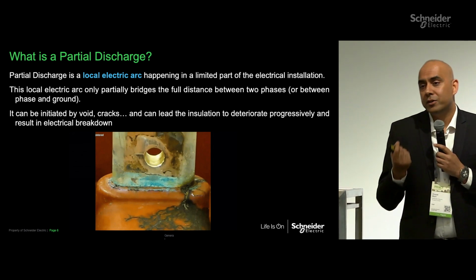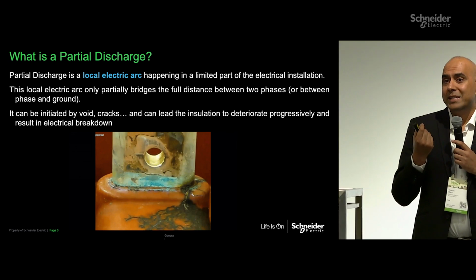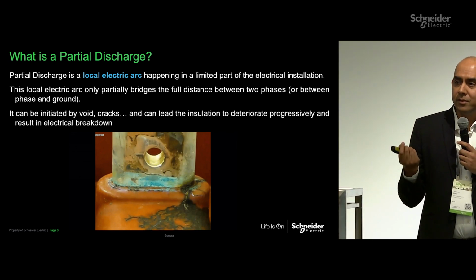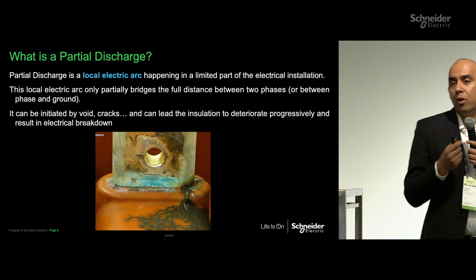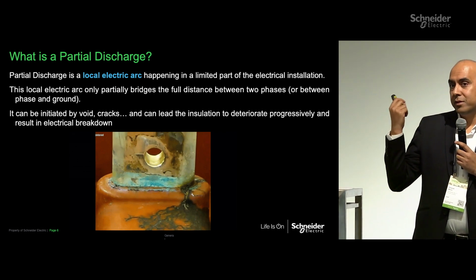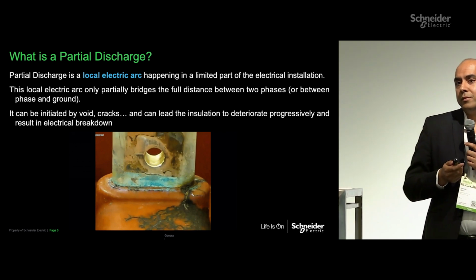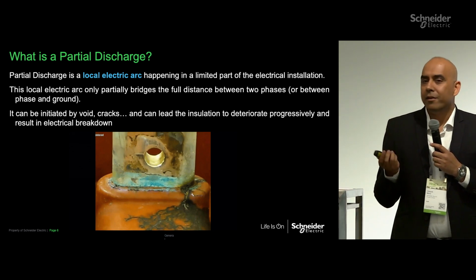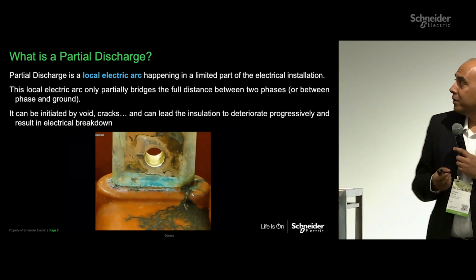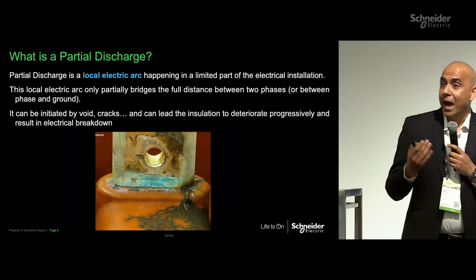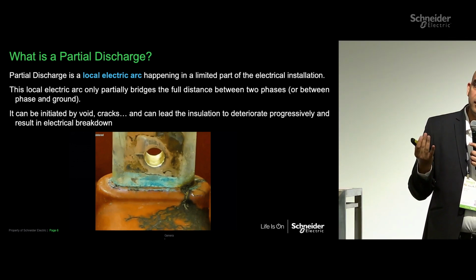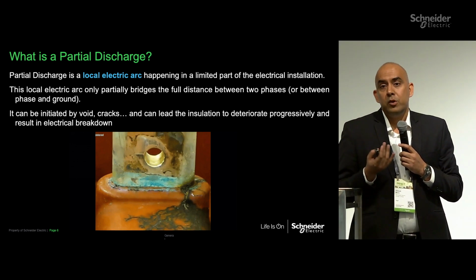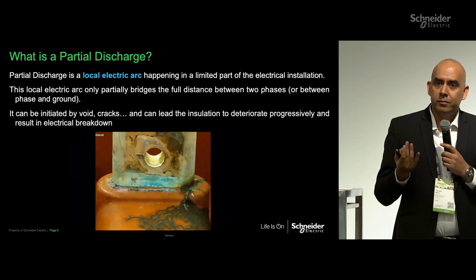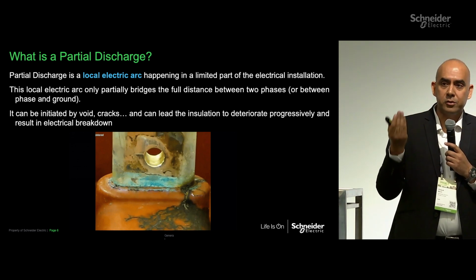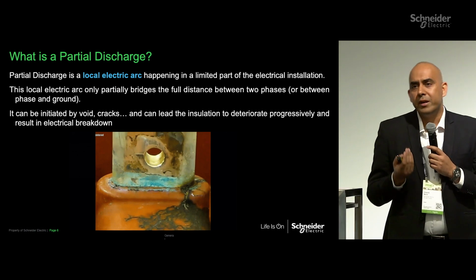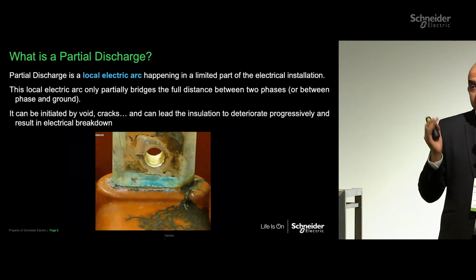Same way, partial discharges are small insulation breakdowns which happen because of various reasons. We will talk about it, and they can cause catastrophic failures, which we have seen earlier in our electrical systems. Typically, in any electrical system, you can have a partial discharge. But the effect, as I said, happens as we go to higher voltages. That means 3.3 kV and above, you can have these issues coming up very strongly. As the voltage increases, the effects can be catastrophic. Maybe at 415 volts, it is not so much because the pressure is much lesser.